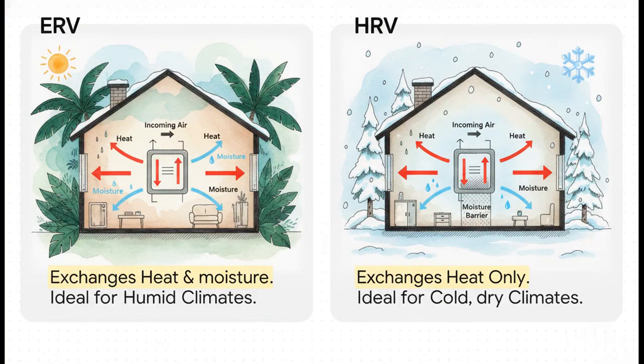But here is where you have to make a critical engineering choice, ERV or HRV. The core difference is that an energy recovery ventilator, an ERV, transfers both heat and moisture between the air streams. This makes ERVs absolutely optimal for hot, humid, and mixed climates, specifically climate zones 1 through 5. They deliver superior long-term value because they automatically manage indoor humidity, preventing really costly moisture damage.